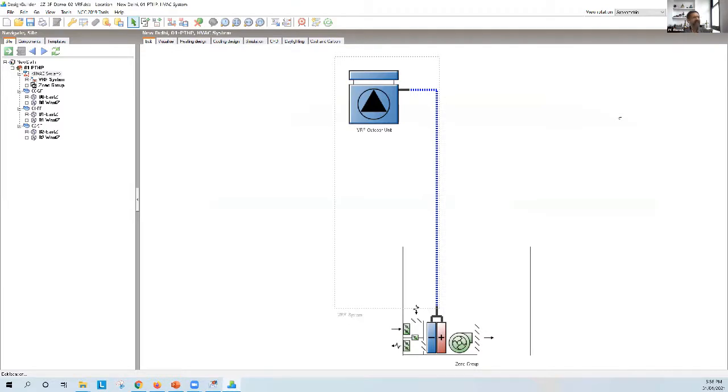I think even in Sydney, I did some numbers, and the number of hours was less than 200 hours across the year where that potential existed. And what it also demands is that if you really want to have a building where one side is being heated and one side is being cooled, it is asking you to design an inefficient building, and that's really not what you want to do, right?